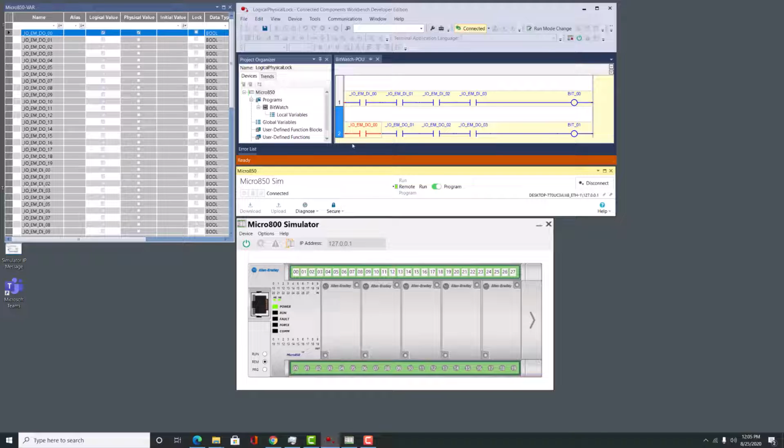And because the logical value is the same, you see in logic here it shows this is true upon instruction, and it's true, which means that bit in memory is on. And it is on because I can see it right here. But that doesn't mean that the output is on. So one thing that we're emphasizing early in this course is to understand the difference between the screw terminals and the bit in memory and the interaction between bits in memory, screw terminals, and the program scan, both input scan and output scan.